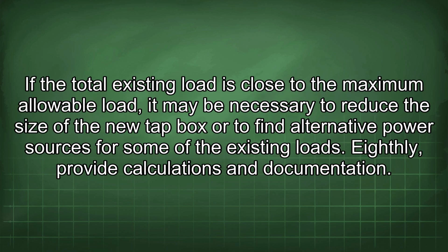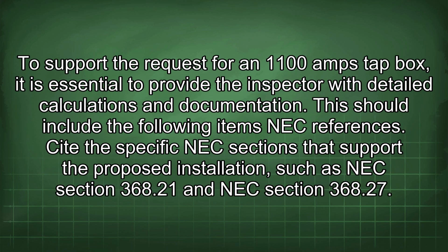If the total existing load is close to the maximum allowable load, it may be necessary to reduce the size of the new tap box or to find alternative power sources for some of the existing loads. Eighthly, provide calculations and documentation. To support the request for an 1100 amps tap box, it is essential to provide the inspector with detailed calculations and documentation. This should include the following items: NEC references.